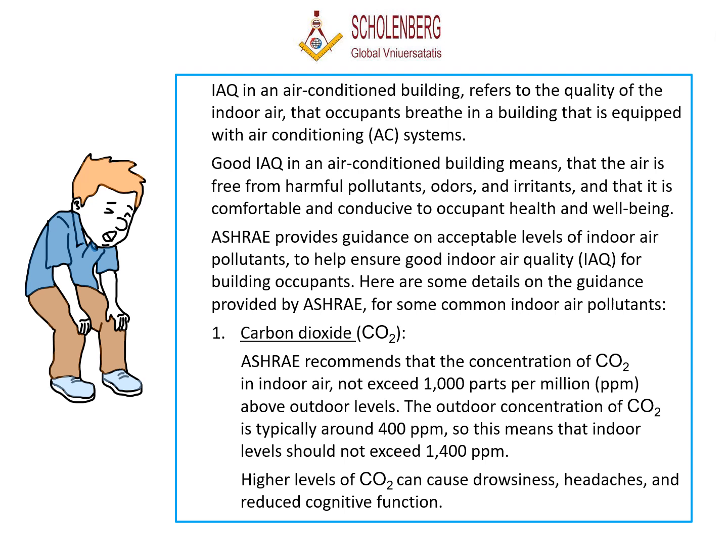ASHRAE recommends that the concentration of CO2 in indoor air not exceed 1,000 parts per million, ppm, above outdoor levels. The outdoor concentration of CO2 is typically around 400 ppm, so this means that indoor levels should not exceed 1,400 ppm. Higher levels of CO2 can cause drowsiness, headaches, and reduced cognitive function.